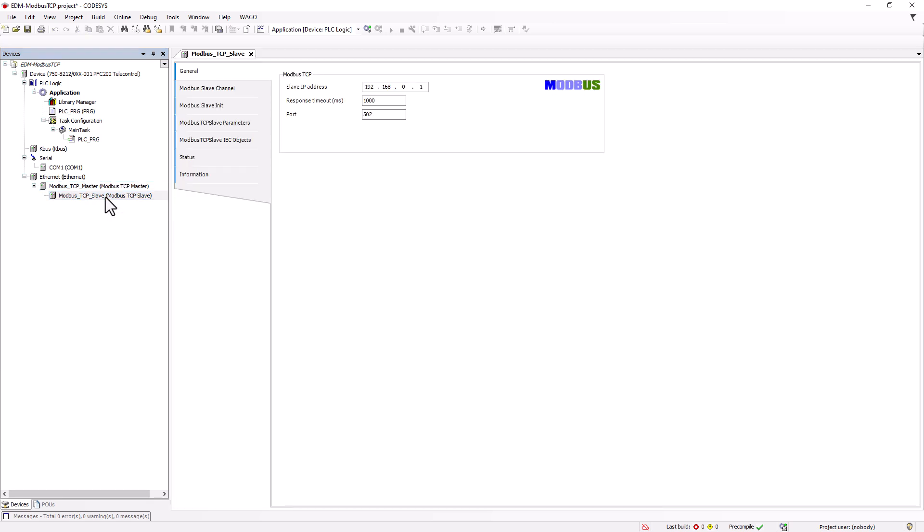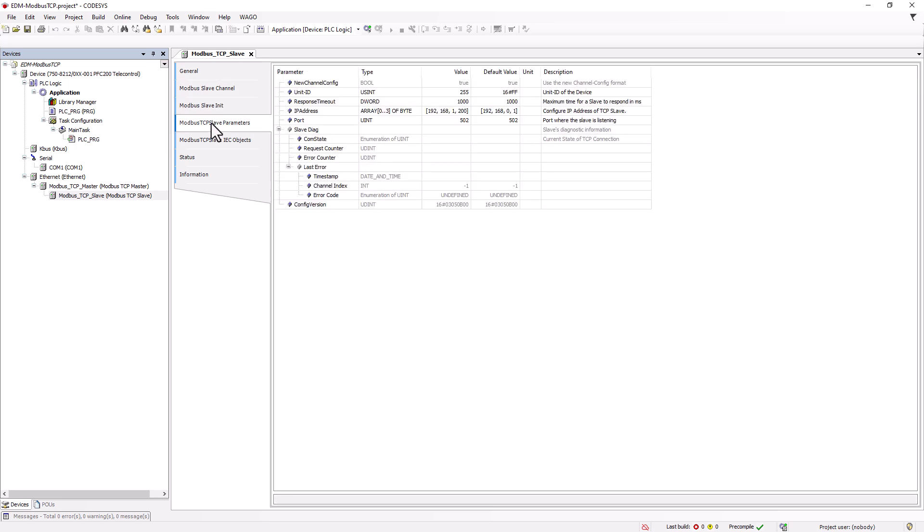We then enter the IP address of the slave, so that of the EDM controller, and check that the other Modbus TCP parameters, such as ID, Port and Update Rate, are set correctly.